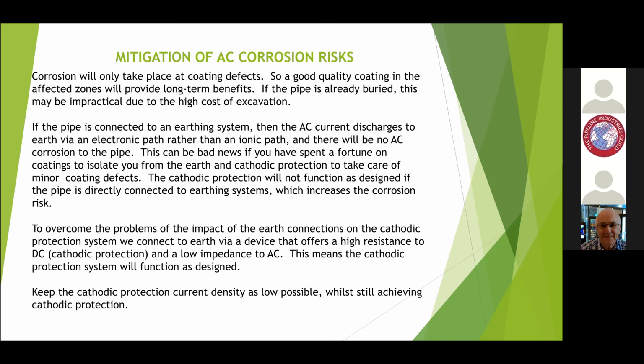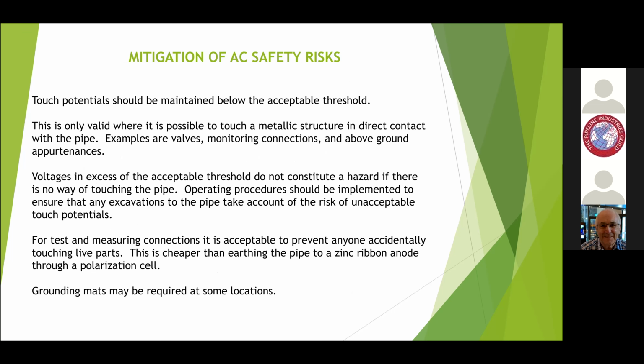So what we have to do is connect the earth of the pipe through a widget that stops the cathodic protection leaving the pipe, but lets the alternating current leave the pipe. Those devices are normally called polarization cells or polarization devices. So you can do that, but of course you have to know where to put those devices and where to put the earthing. And that normally we do by modeling, which we'll talk about a bit later. We also, to fulfill one of the requirements of the AC protection criteria, need to keep this current density as low as possible, which is not always the case. Many pipes have too much cathodic protection current.